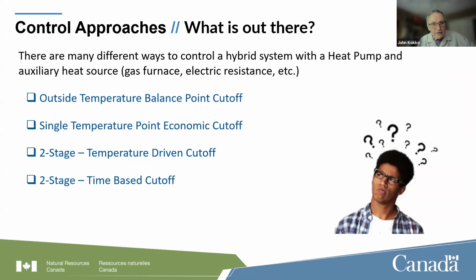So what we're going to talk about are four different heat pump control options. They're known as outside temperature balance point cutoff, single temperature economic cutoff, a two-stage temperature-driven cutoff, and a two-stage time-based cutoff. And we'll explain each one of those as we go. And like I say, the examples are for gas backup heat, but it can be used for either the electric or the gas.